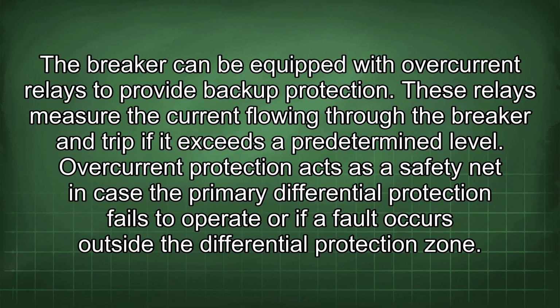The breaker can be equipped with overcurrent relays to provide backup protection. These relays measure the current flowing through the breaker and trip if it exceeds a predetermined level. Overcurrent protection acts as a safety net in case the primary differential protection fails to operate or if a fault occurs outside the differential protection zone.